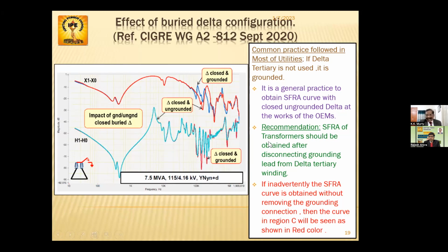It is recommended that the SFRA of the transformer should be obtained after disconnecting the grounding lead from the delta tertiary winding. If inadvertently the SFRA curve is obtained without removing the grounding connection, then the curve in the region C will be shown in red color. So if delta is closed and grounded, you will find this difference. This blue one is the ungrounded curve. So this you can see.